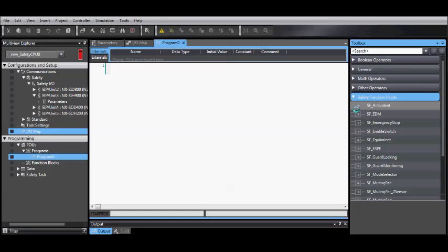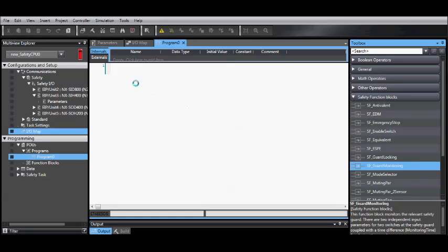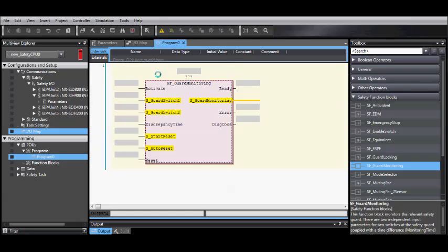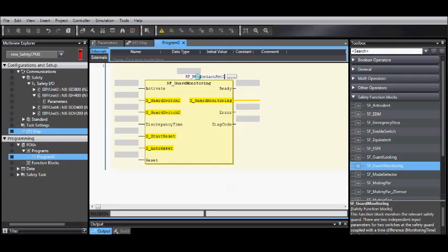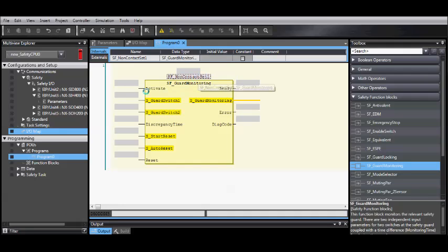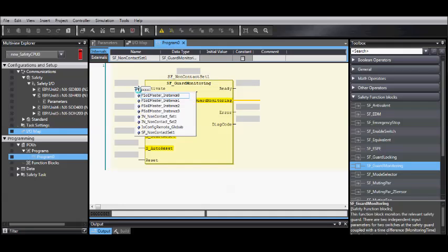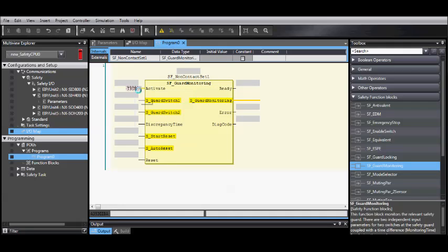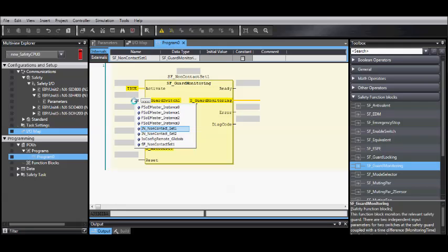On the right-hand side in the toolbox, go to Safety Function Blocks, and select Guard Monitoring. Drag and drop this until you see the start here, and then let go. Give your function block a unique name. For Activate, if you are not using the Safety Connection status, just enter TRUE.